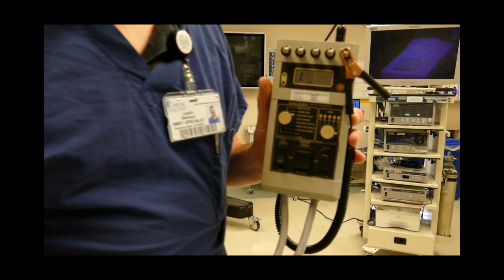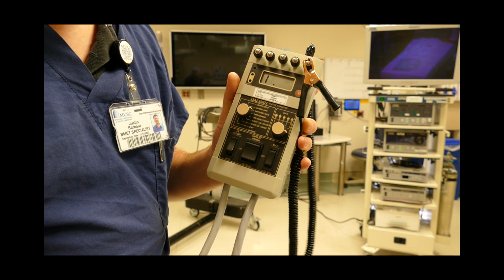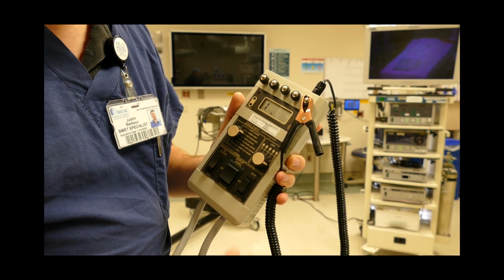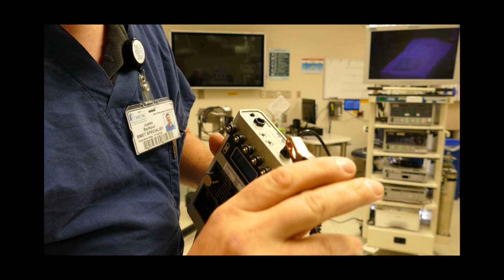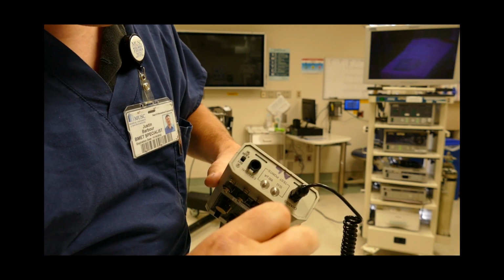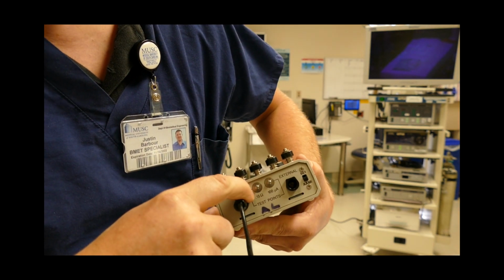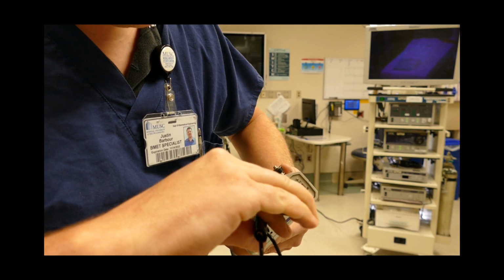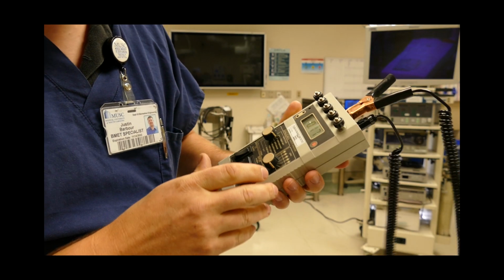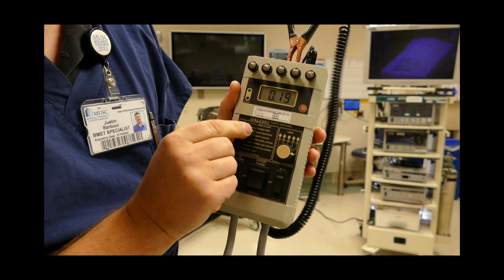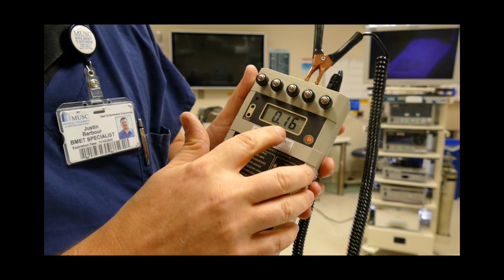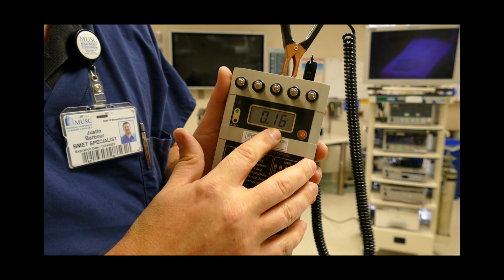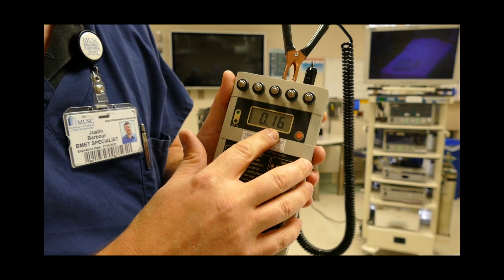The first thing to do when testing out electrical safety is you have to check your meter. So what we're going to do is we're going to set this up on 0.15 ohm. You can see it right here. Connect it there. And your dial is going to be on earth resistance. And on the meter, it should show pretty close to 0.15 of an ohm.